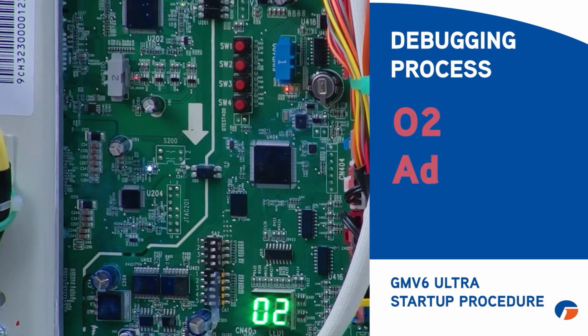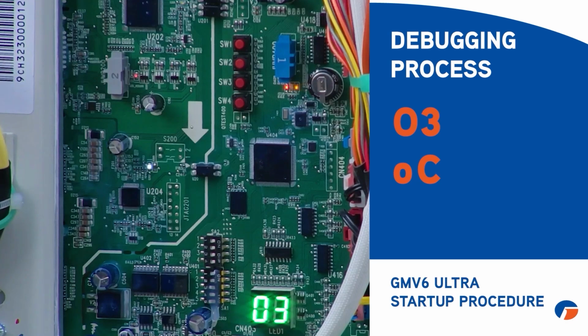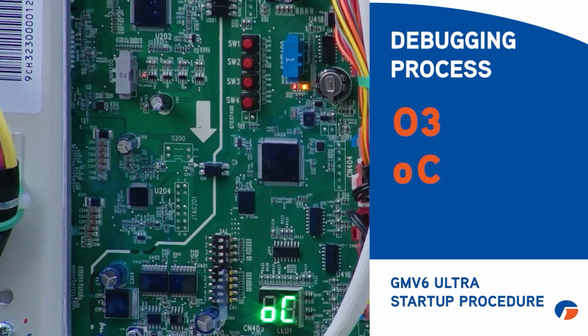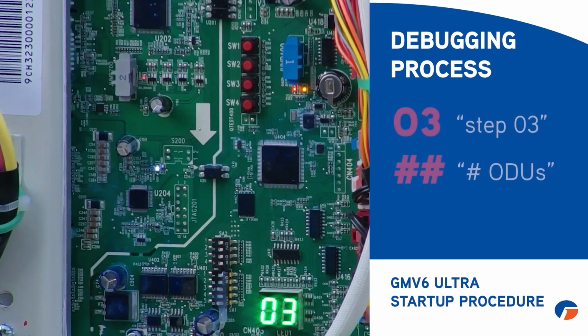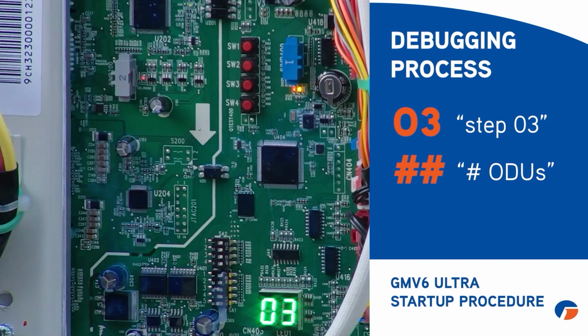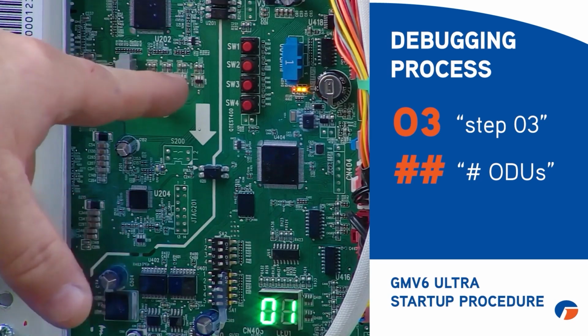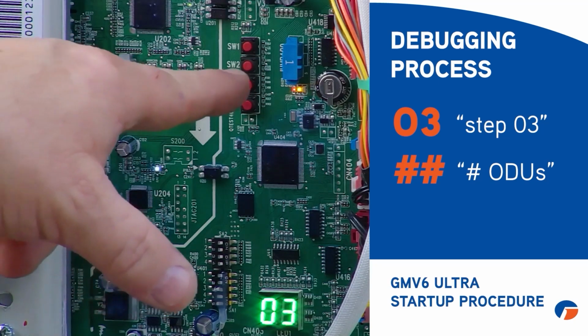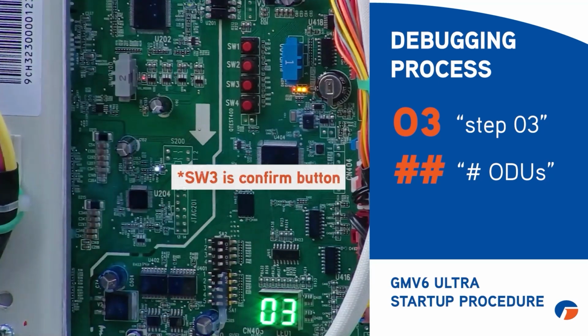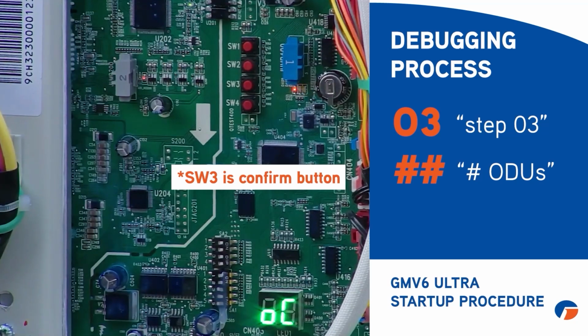O2 AD, O3, OC, O1, O3. That means step 3, 1 outdoor unit. That's what that means. We might have to hit confirm on this one. If that's the case, SW3 one time, and it should go further on.